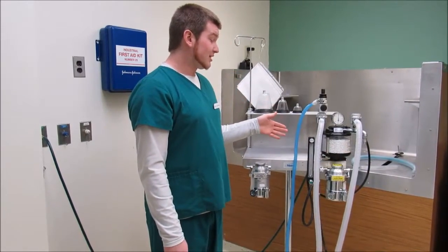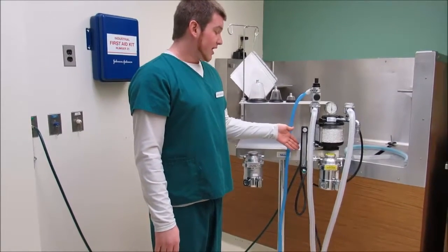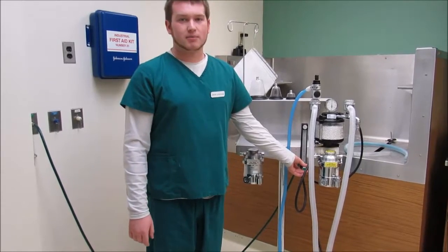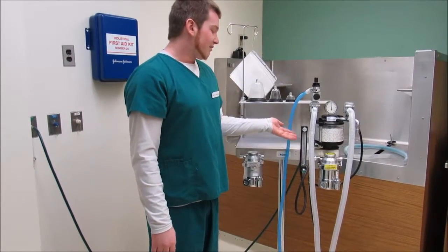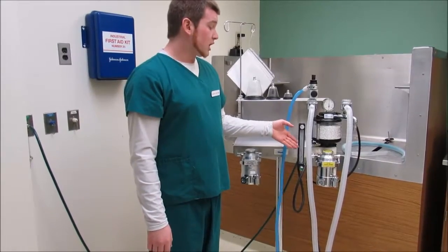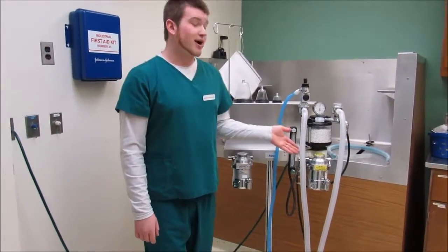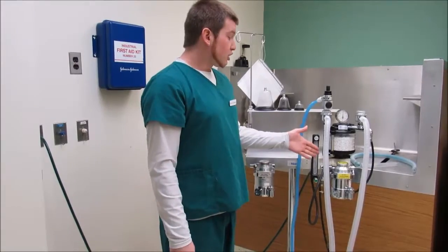Okay, going back to the flow meter now. So the flow meter is right here, and we generally at SUNY Delhi like to say 1.5 is our safe number. And so we usually run at about 1.5. So it goes from the flow meter to the precision vaporizer. The precision vaporizer compensates for humidity, temperature, and back pressure.